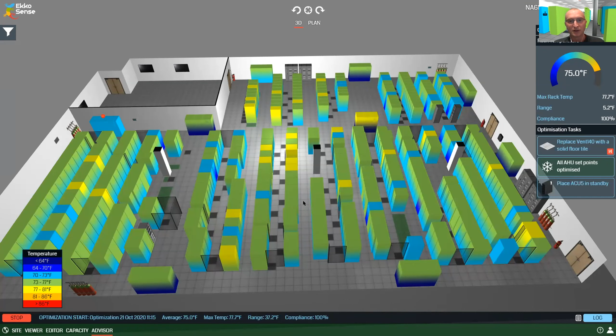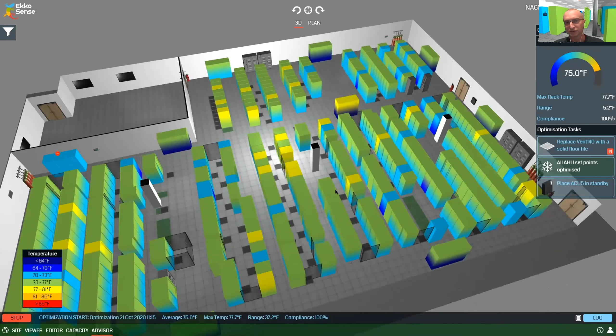So a typical story is an optimization would be carried out, make great savings, airflow is fantastic, and it's all set up. But then typically over time, just by not updating the optimization, that perfection kind of drifts away. Airflow management, airflow efficiency starts to go down again. Temperatures start to creep around. The range of temperatures from top and bottom starts to drift around. So this module has been designed specifically in order to keep the optimization tracking at the level that you want it, so you can actually maintain those efficiency gains and any of those savings that you've made. So this is intended essentially to be used weekly, if not daily, just to keep on top of thermal and airflow conditions within the room.